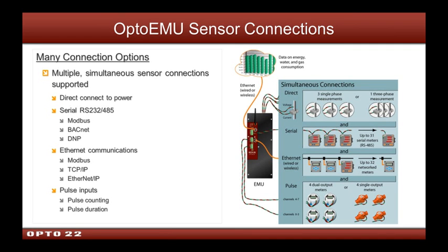So you use a current transformer, and you would also take the voltage in, and you would bring that into the OptoEMU sensor. And again, there we could do 3 single phases or 1 3-phase. We have the serial and Ethernet connections to talk to third-party devices, and for the building mains or a gas meter or a water meter, we accept pulsed outputs from these meters. And we could do up to 4 of those. There's 2 types of meters we've seen out there. They either have 2 outputs or a single output, and we can accept either type. So that kind of goes over the ground level connections of how we capture the data.